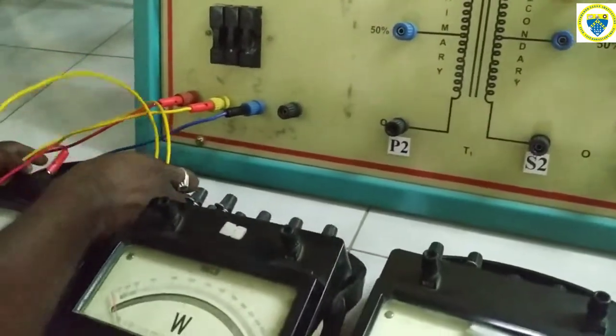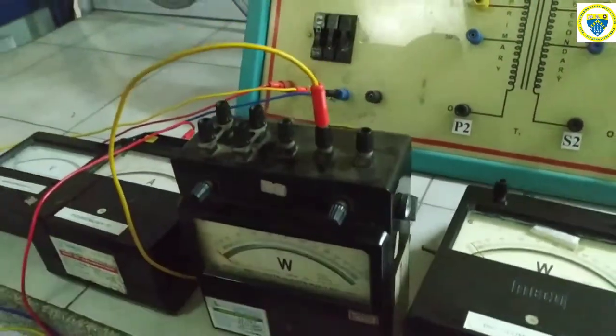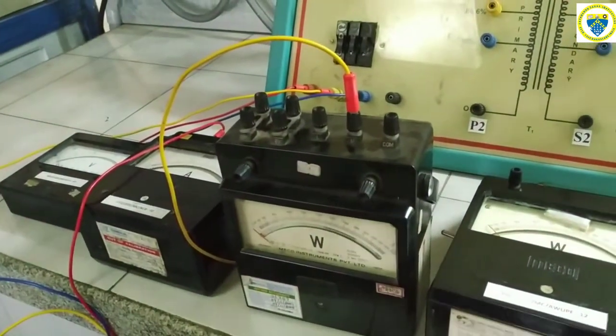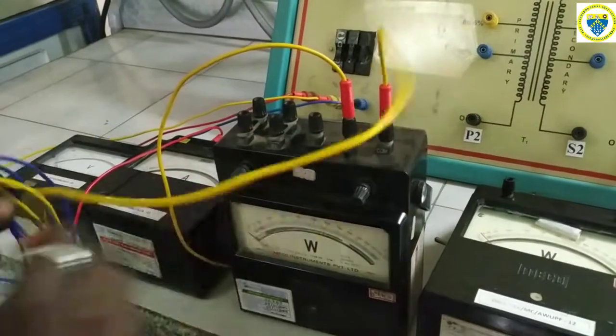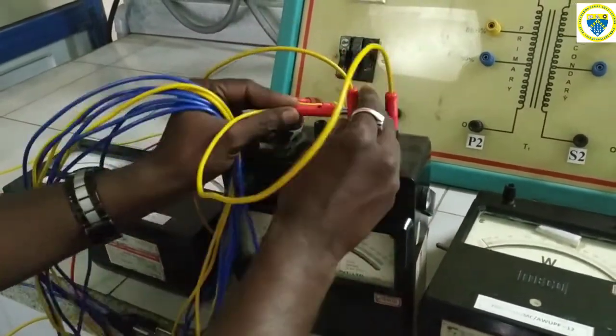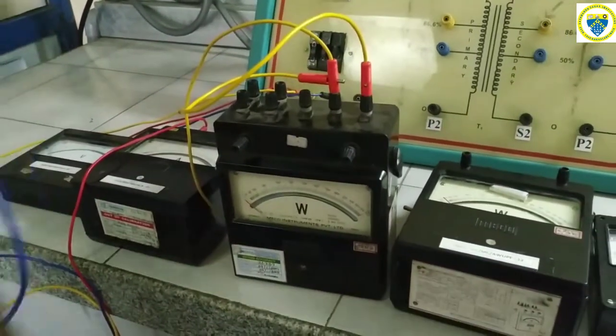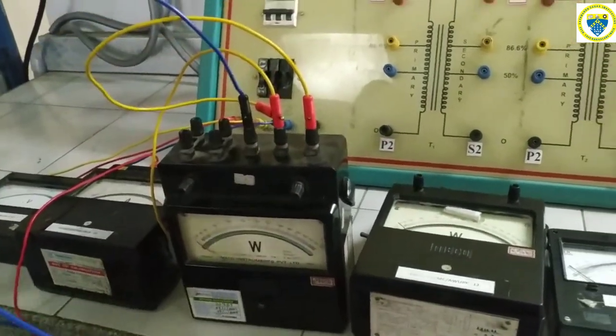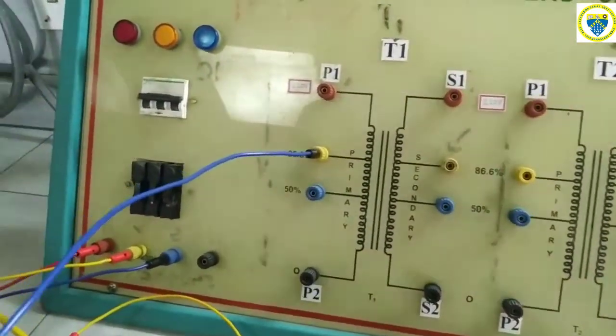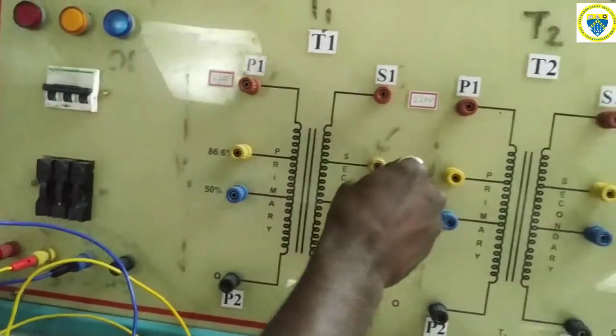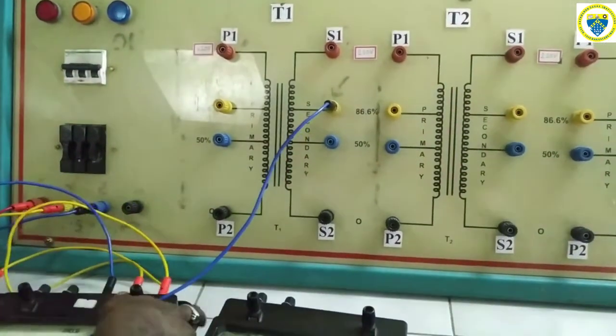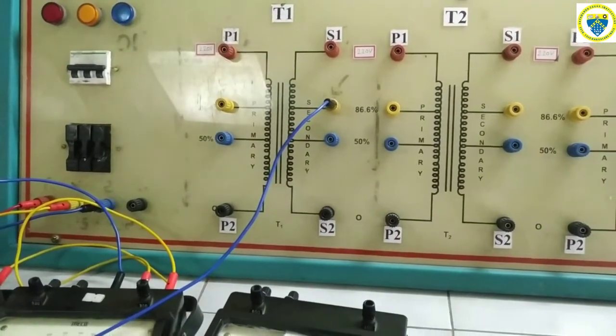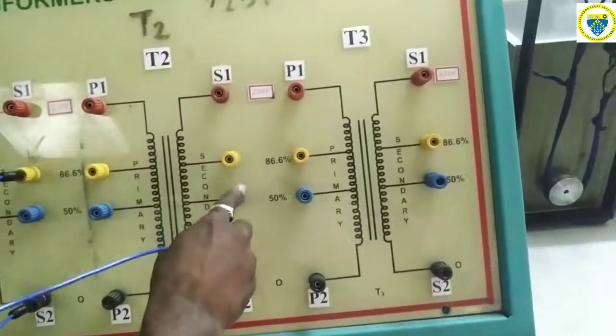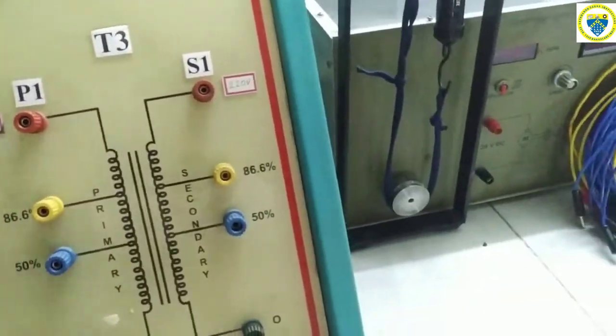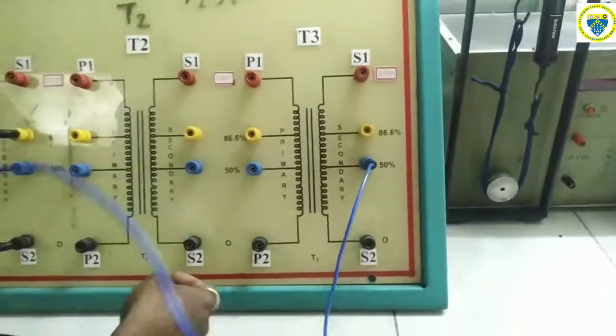First terminal of the ammeter is R phase, and then the ammeter's next terminal should go to the wattmeter M terminal, and then MC should be shorted, and next the L terminal should go to the main transformer tapping of 86.6%. Now on the secondary side we should give S1 S2 side, and then from S2 it should go to the teaser transformer 50% side.